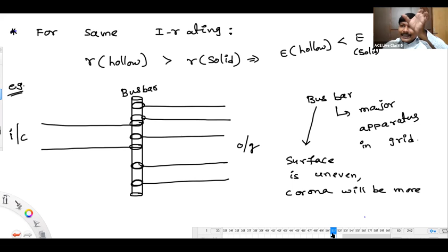Not only one joint, we have many joints on the bus bar, so the bus bar will experience very high electric field intensity. So corona will be very, very high on the bus bar. Because of joints and fine, sharp edges, corona is more in the bus bar. So we have to select the conductor in such a way that it experiences less corona. In that view, I am selecting the hollow conductor rather than the solid conductor, because the hollow conductor has less field intensity compared to solid. So I think you are clear now. Is it okay?